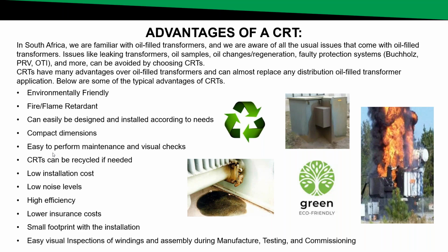Cast resin transformers can be recycled if needed after their lifespan has been reached. 90% of cast resin transformer material can be recycled. Cast resin transformers provide lower installation cost. If you think about oil transformers, you have to build bund walls, you have to build sumps. Cast resin transformers can basically be put into a room or an enclosure, as previously mentioned, and operate under those conditions. Cast resin transformers also have low noise level. They have high efficiency, and insuring a cast resin transformer or the installation reduces the insurance cost due to the lower risk of fire and spillage.